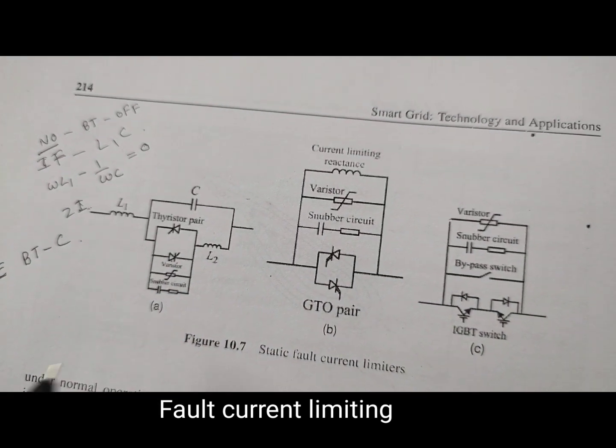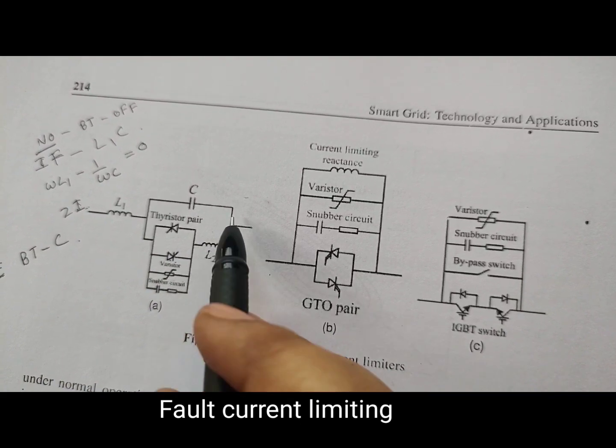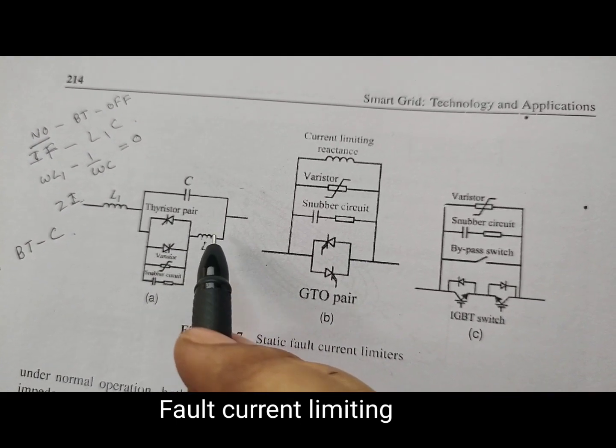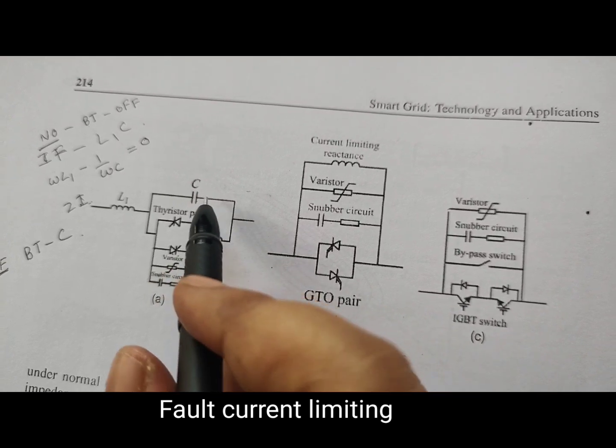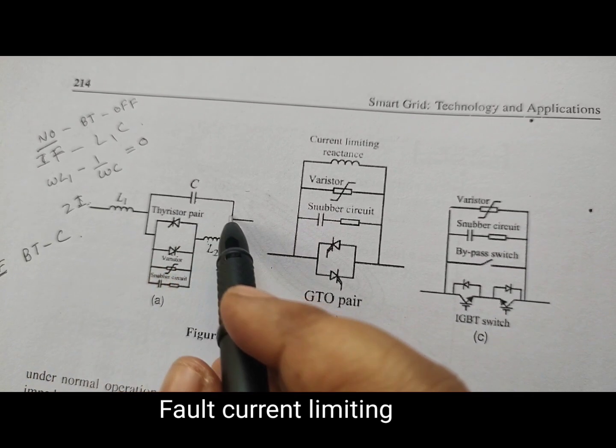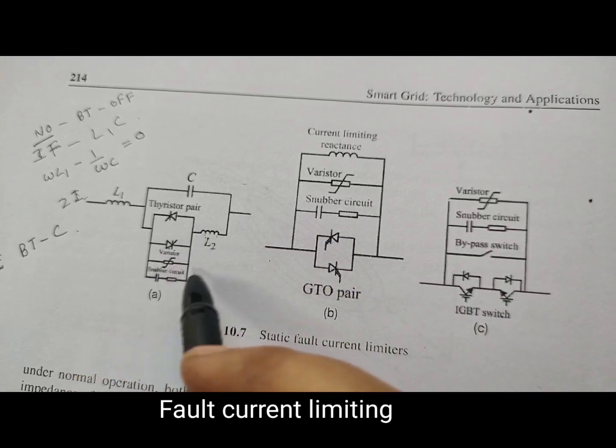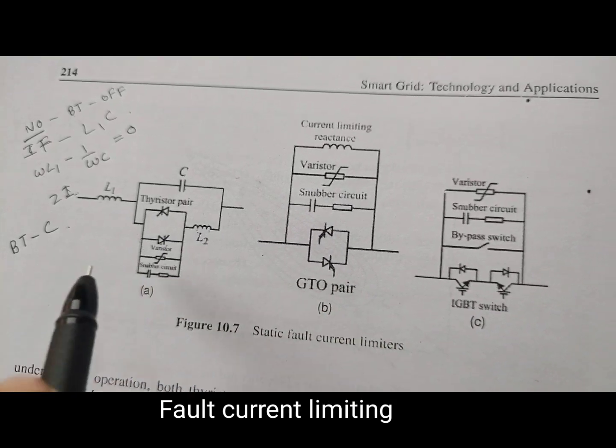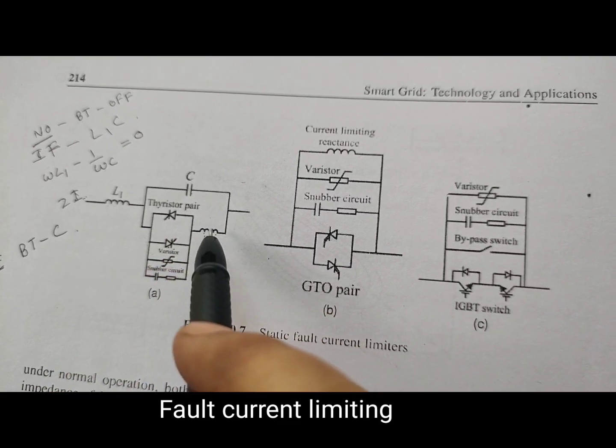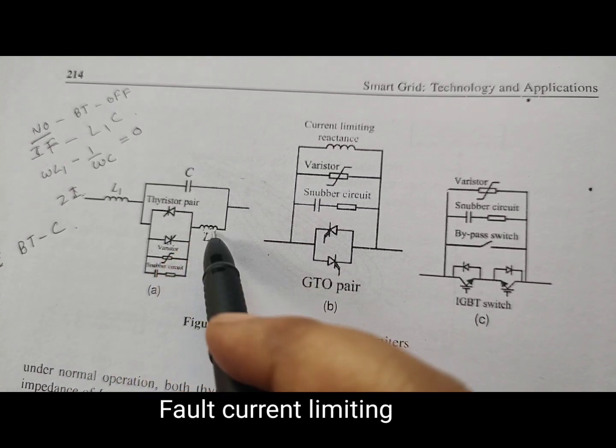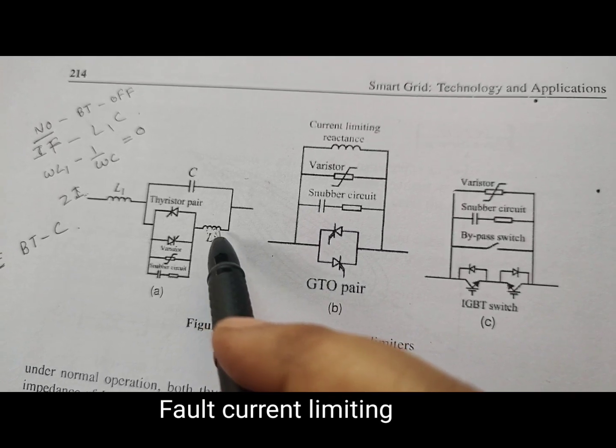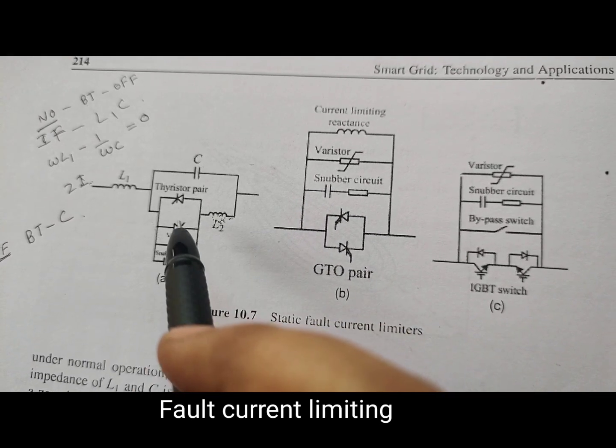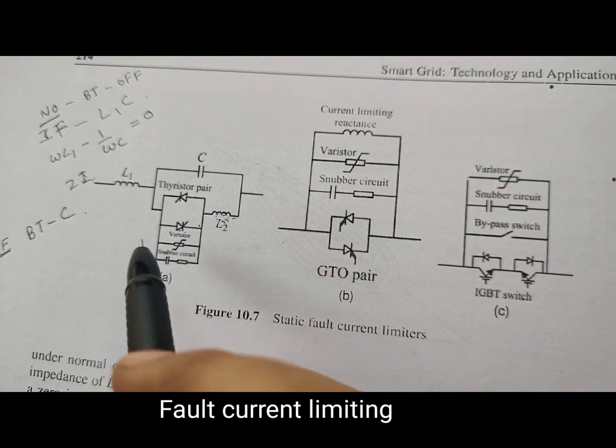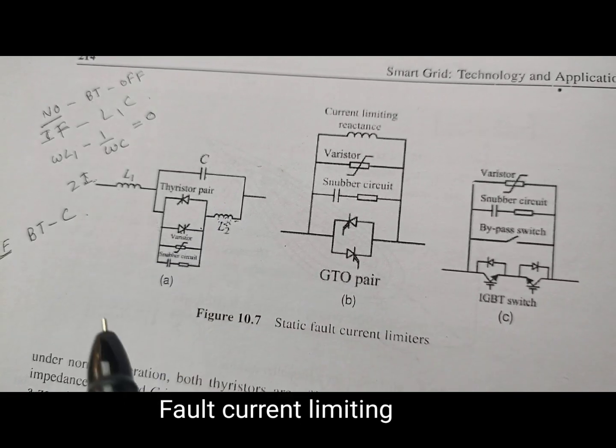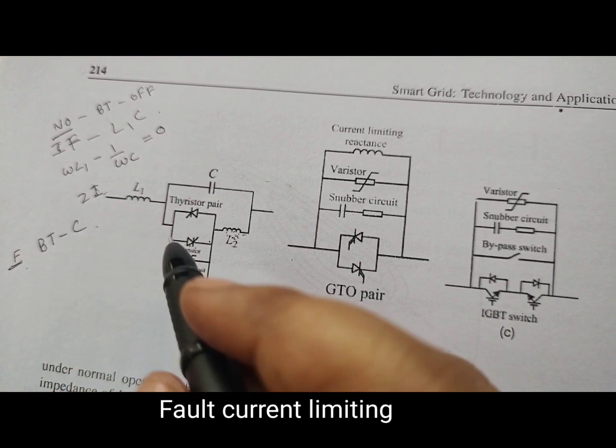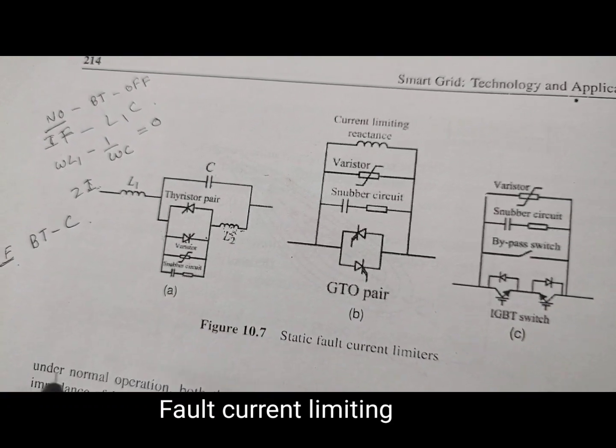In that case, L2 is connected in parallel with the C. During normal operation it is not related at all, but during the fault condition it will be connected in parallel. L2 is connected in parallel with C, thus increasing the total inductive impedance in series with the line.